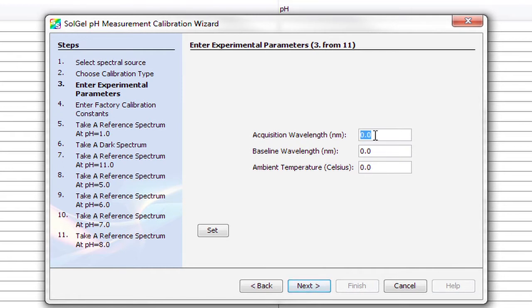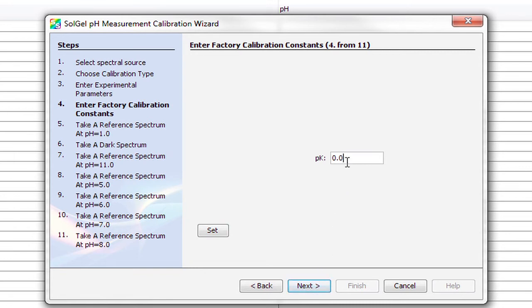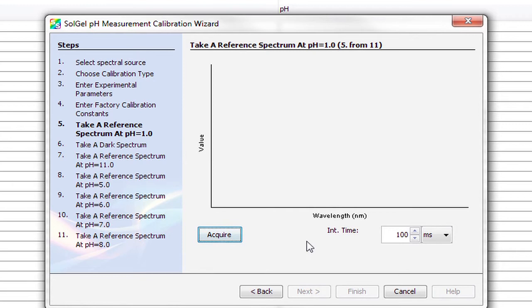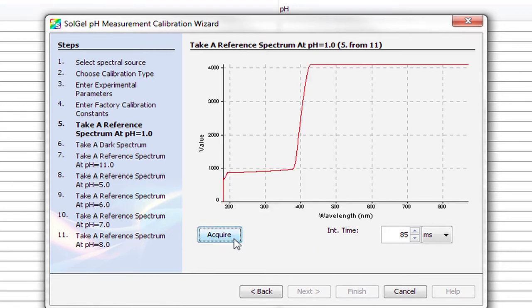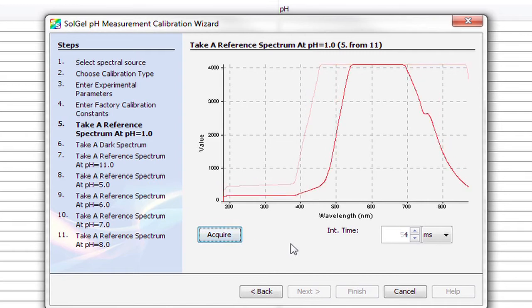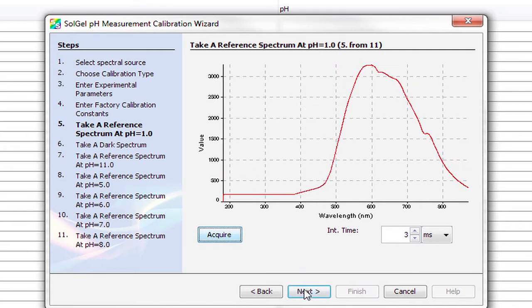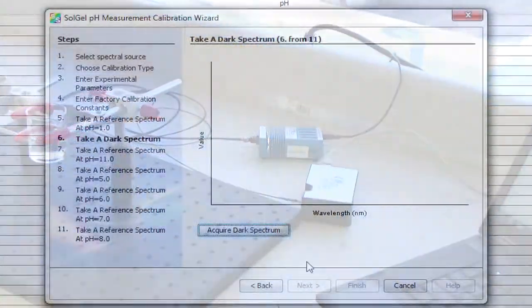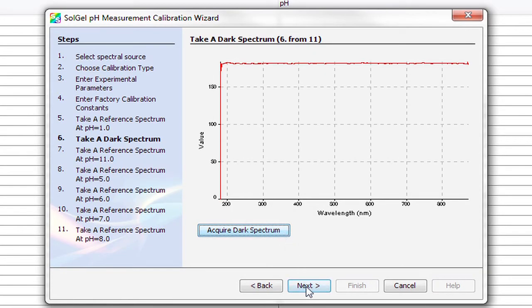Enter 620 for acquisition wavelength, 750 for baseline wavelength, and whatever your operating temperature is for the ambient temperature. Click Set and then click Next. Enter the pH value found on the box of pH patches. Click Set and then click Next. With the sensor exposed to pH 1, click the Acquire button and allow the system to adjust the integration time automatically. Once it is stabilized, click Next. Block your light source, click Acquire, and then click Next.